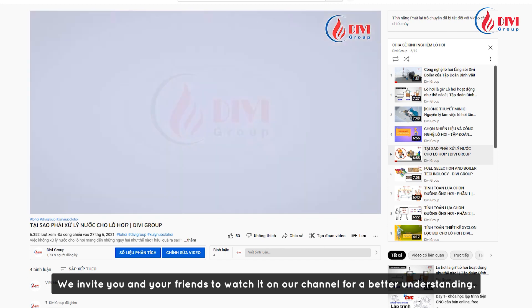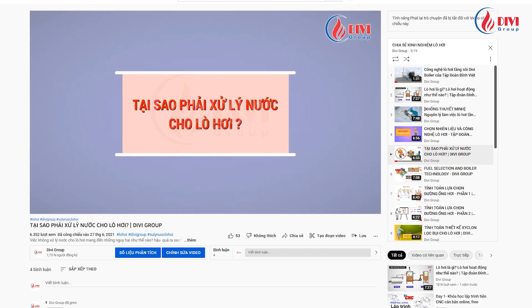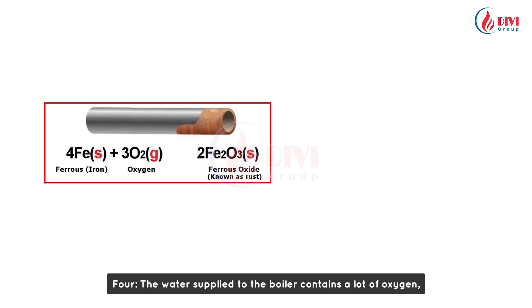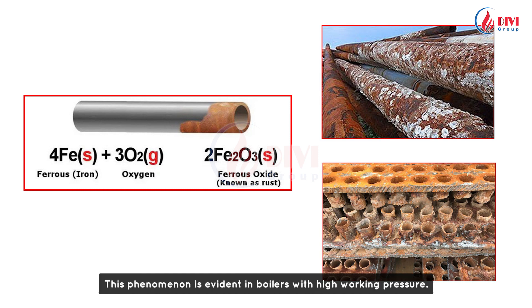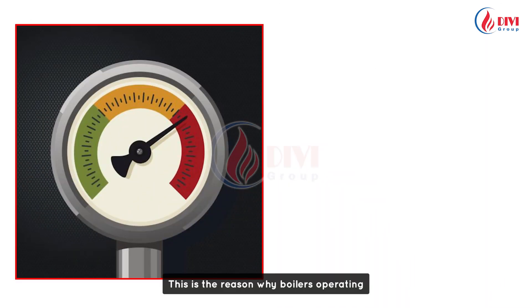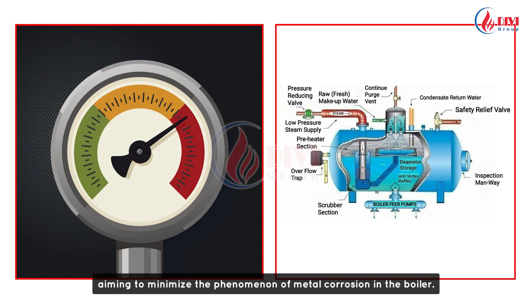We invite you and your friends to watch it on our channel for a better understanding. Fourth, the water supplied to the boiler contains a lot of oxygen, causing oxidation of the iron and steel and leading to corrosion inside the boiler. This phenomenon is especially evident in boilers with high working pressure. This is why boilers operating at high pressures are equipped with deaerators to remove oxygen from the feed water, aiming to minimize the phenomenon of metal corrosion in the boiler.